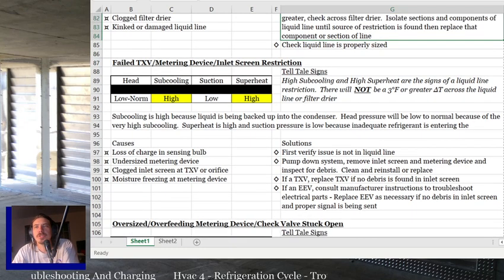If you check across the liquid line and you do not have a liquid line restriction, then you have a failed TXV or a failed metering device in some way, shape, or form, or the inlet screen to that metering device is restricted. So we'll have the same problems as a liquid line restriction: low to normal head pressure, high subcooling, low suction pressure, high superheat. The telltale sign, though, is the high subcooling with the high superheat but there will not be a 3 degree or greater delta T across the liquid line or filter dryer.